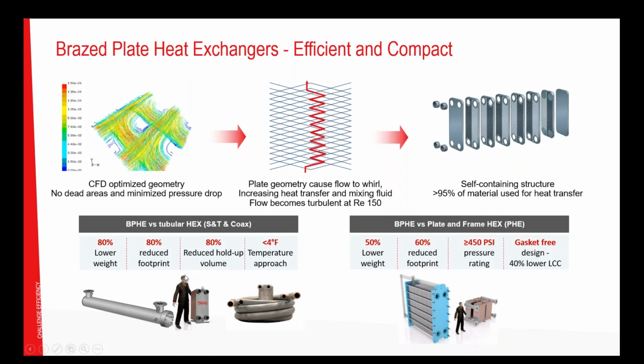And you might ask, okay, why is hold-up volume interesting? It's interesting because the more thermal mass you have inside a system, the longer it takes to update the temperature, to make changes to the temperature. If we have a lot of weight of fluid inside here, and there is a change of the temperatures in the process, it will take time before the heat exchanger with a lot of thermal mass will be able to update that. With a brazed plate heat exchanger having a very small internal volume, it's easier to have a more direct and fast update of temperature control of the process, make it more exact and more direct.